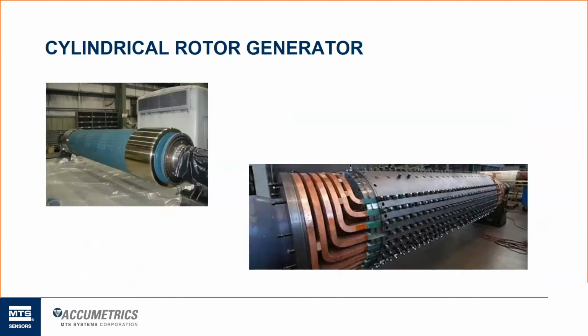So most gas and steam turbines use what's called a cylindrical rotor. You can see that here. I'm going to get my little cursor available here. So these consist of this cylindrical style rotor. There's a bunch of forgings that are slotted to accommodate the turns of wire, which you can see in the copper conductors. They're about a 3 or 4 inch wide copper bus bar, copper conductor that run down into these dovetail forging grooves and form a giant turn of wire, just like a motor or generator.